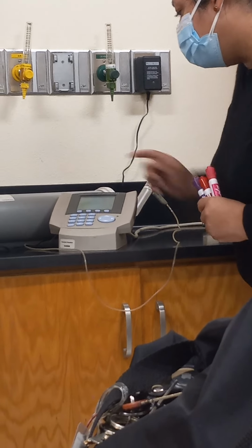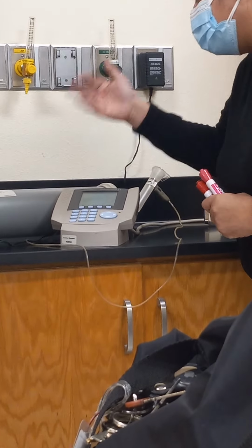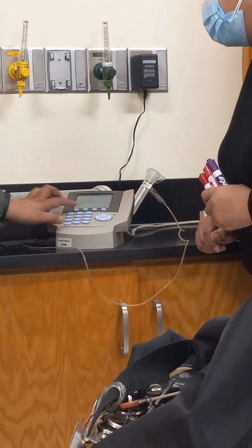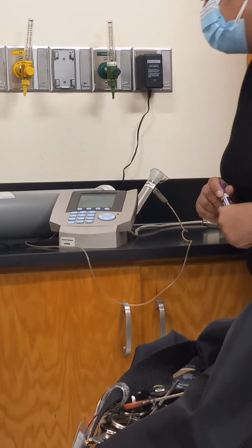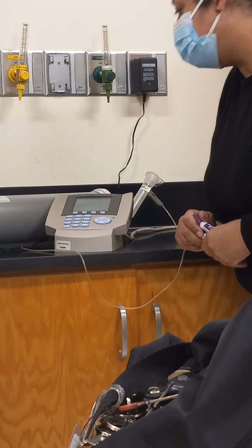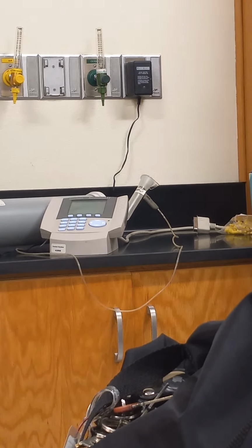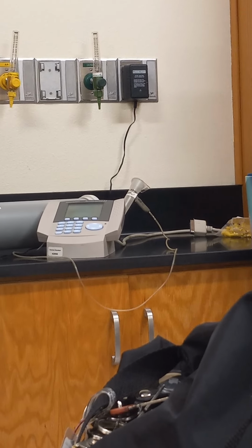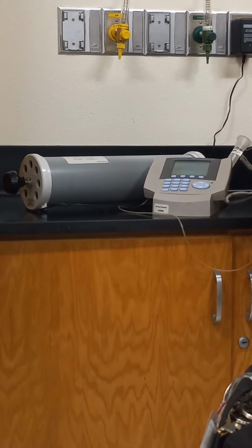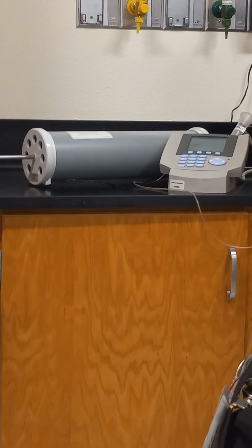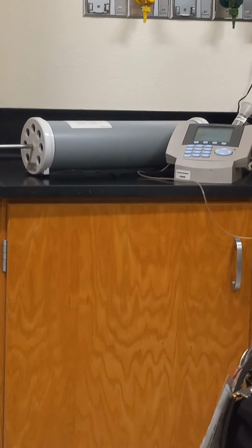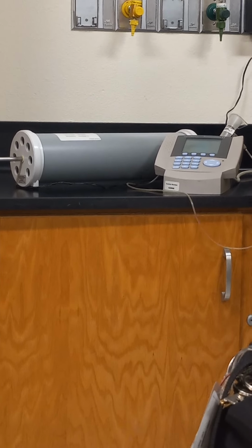It says attach sensor to syringe and pull plunger out when it's done and hit proceed. It's zeroing in progress, so don't touch it. Now push the plunger smoothly over 2 seconds. So literally 2 seconds, 1 1,000, 2 1,000. And then for inspiratory, go ahead and pull it out.